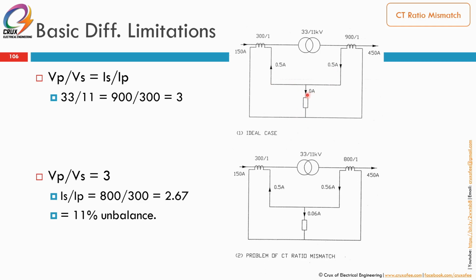This is the ideal case. Normally our CT is not chosen based on this. CT size is based on the full load current of the transformer, or 1.2 to 1.3 times the transformer full load current. So in this case 300 on the primary, but the secondary uses 800. When it converts, primary 150, the secondary gets 450 amp because of the transformer turns ratio. The primary reads 0.5 amp on the secondary, but because the CT turns ratio is different, the 450 amp on the secondary side is read as 0.56 amp. The primary side has no problem, but after conversion there is some differential current: 0.5 minus 0.56 gives 0.06 amp.